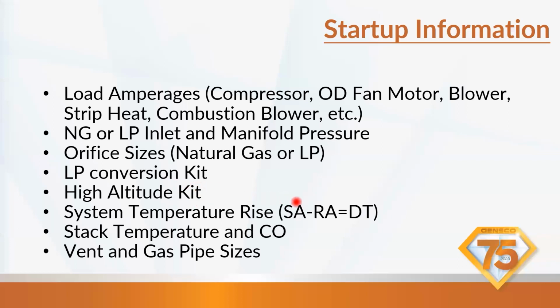System temperature rise, which is your supply air minus your return air equals your delta T. I'll touch on what I used to like seeing in the field as far as delta Ts also. Your system temperature rise and the recommended temperature rise in gas furnaces are stated on the data plate. So you can always refer to the data plate as far as the temperature rise that you want to see through the furnaces, design temperature rise, your stack temperature, your CO, your vent and gas pipe sizes.